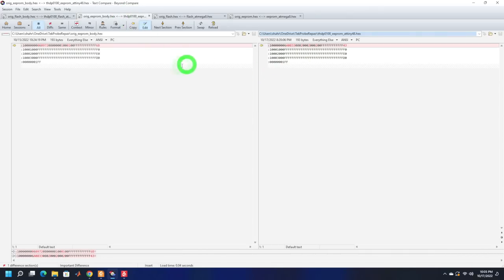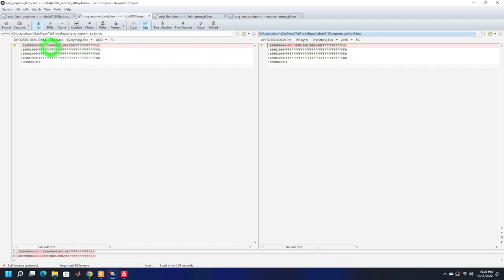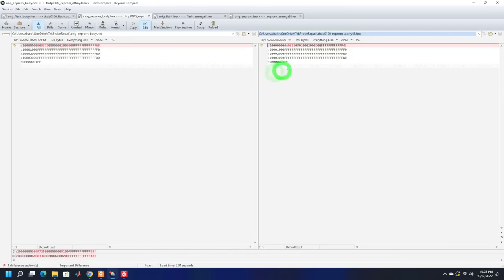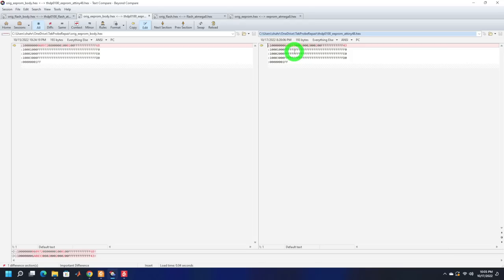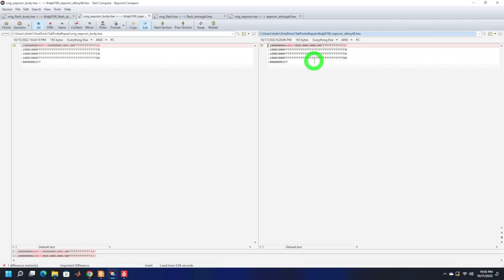The only thing that is left is just the EEPROM of the body. I compared that and there is where we see some more differences. There is no more serial number in this, and you can see that the probe that he has sent me and my probe have very different first line content of their EEPROM. I have no way of knowing what this means. I put this into the ASCII interpretation, it makes no sense, it's just gibberish. The probe is using this information to do something, I just don't know what. The only thing I need to do is to download this one into my probe and see what happens, see if it boots correctly or if it identifies itself as a 100 model or not.